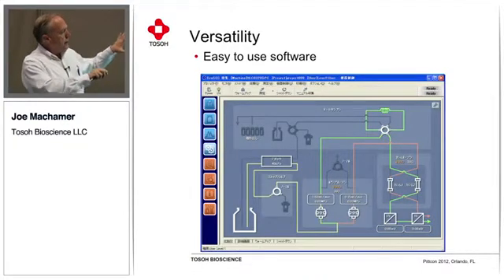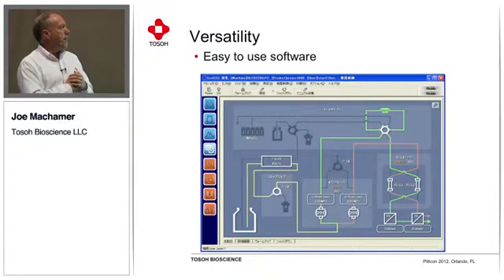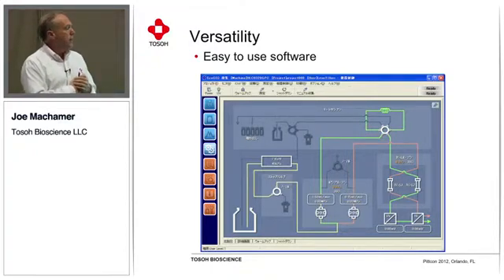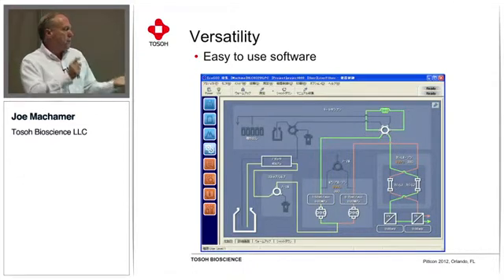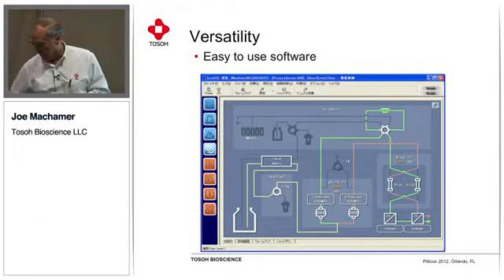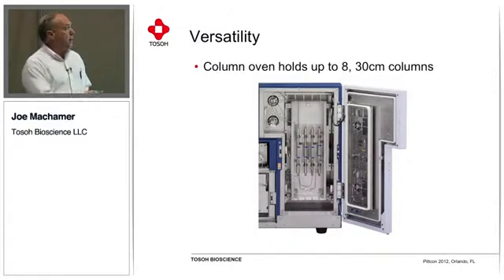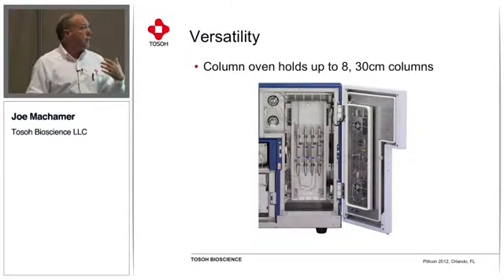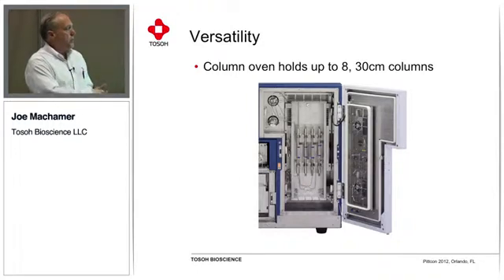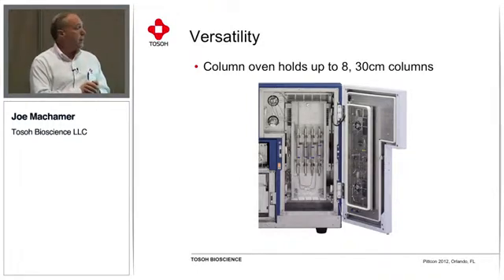Also, the instrument and the software are all designed around being optimized for GPC-type analysis. So it has all the calculations needed for MW, MZ, and MN, and a very nice interface where any changes in valve positions, injections, or autosampler are reflected on the screen. A very nice feature also is that the column oven is unique in that it can hold up to 8 30-centimeter-long columns. So if you are in a lab where you're using lots of different columns, you can keep them all at the same temperature very conveniently with this column oven.